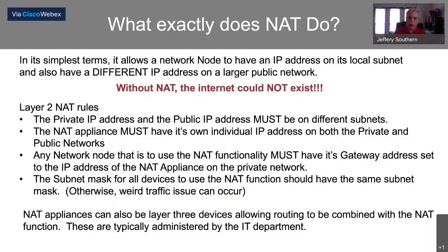The SCADA system says, I want to read this tag value. The processor says, okay, here's the tag value. Oh wait, you're not in my subnet. I don't know how to send that back to you. So I'm going to send it to the NAT, which is my gateway address. And the NAT hopefully knows how to send it back to the SCADA system so he gets his response. That's the whole concept of how NAT works.